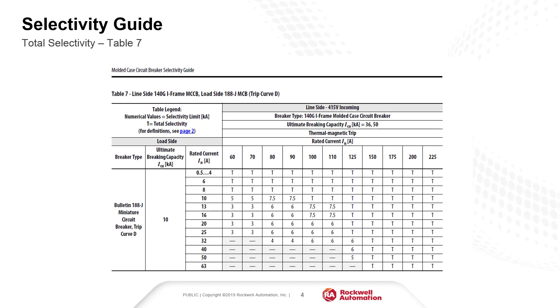Assuming the line side is around 415V with a current rating of 100A for the 140G and a 10A current rating for the 188J breaker, we can determine that we have total selectivity guaranteed for all circuit current values up to the ultimate breaking capacity between the two breakers — in this case, 10 kA.